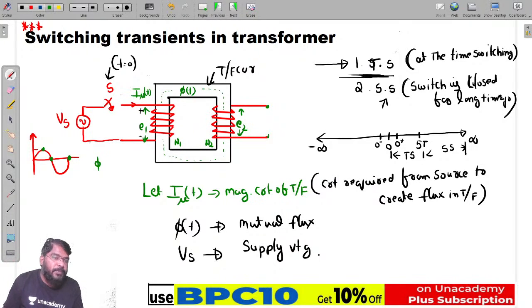Suppose if the switch is closed at the instant supply voltage equals zero, or the zero crossing point, that is pi or 2 pi and so on, and we close the switch at that time, then what happens in the transformer? The transformer core goes into deep saturation, which demands high magnetizing current from the source.